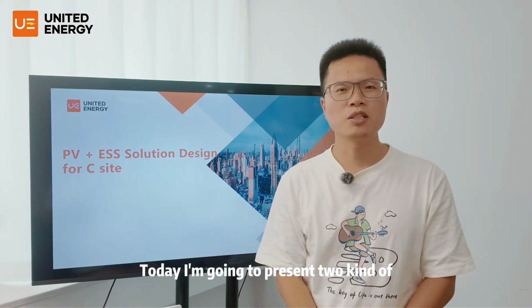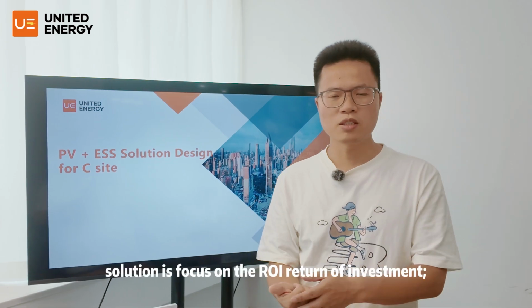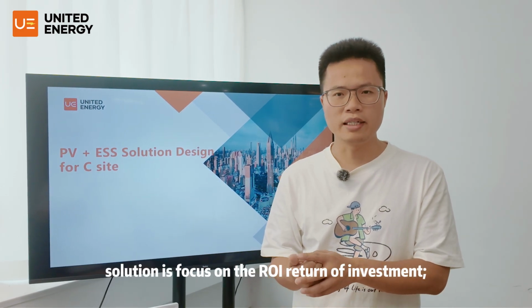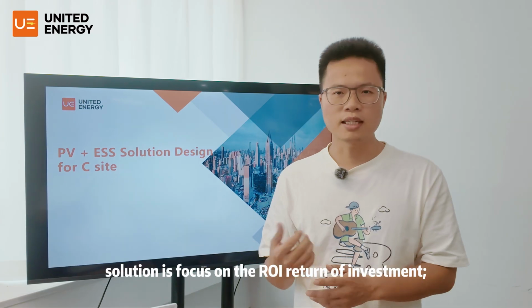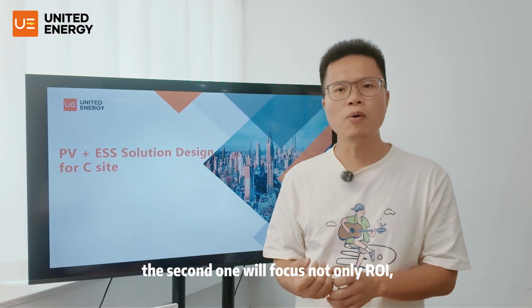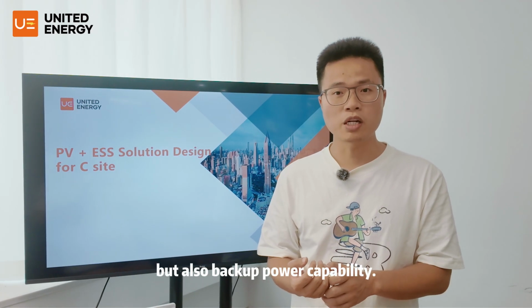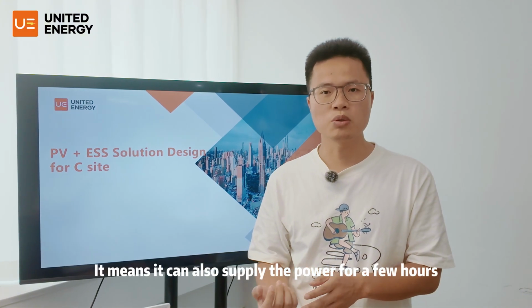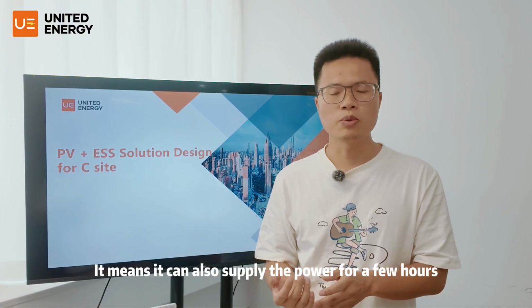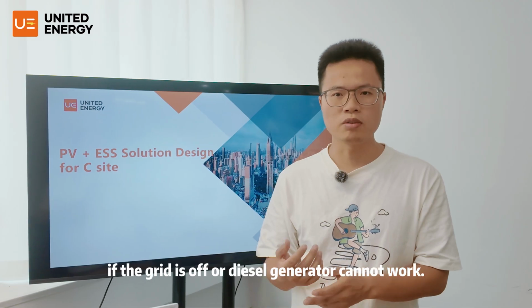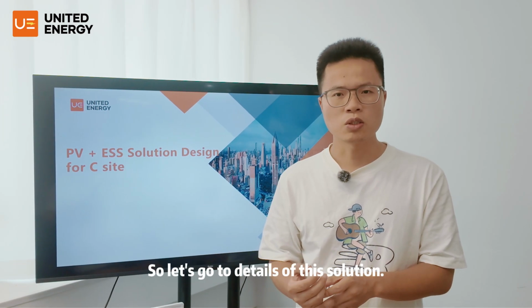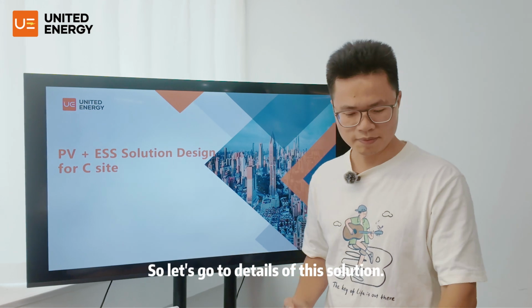Today I'm going to present two kinds of PV plus ESS design for a commercial scenario. The first solution focuses on the ROI, return on investment. The second one will focus not only on ROI but also on backup power capability. It means it can also supply power for a few hours if the grid is off or the diesel generator cannot work. So let's go to the details of this solution.